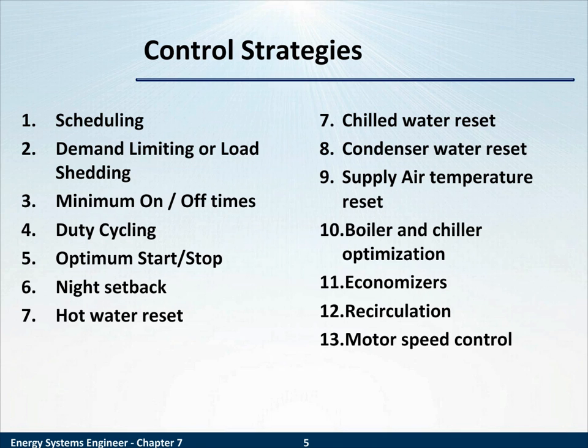The next four, hot water, chilled water, condenser water, and supply air, are what's called resets. And all the reset strategy does is allow something to change as the demand for that thing changes. So hot water reset allows you to vary hot water temperature as the demand for hot water changes. Chilled water reset allows you to change the temperature of chilled water as the demand for chilled water changes, and likewise with condenser water or supply air.